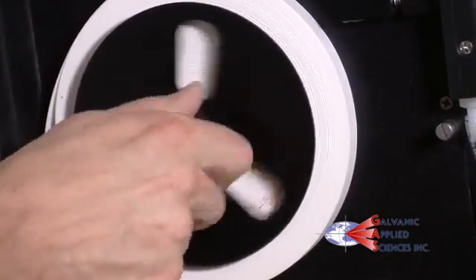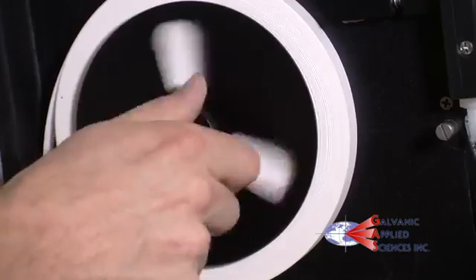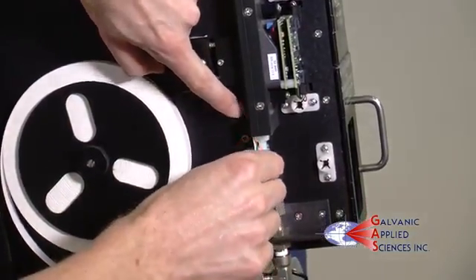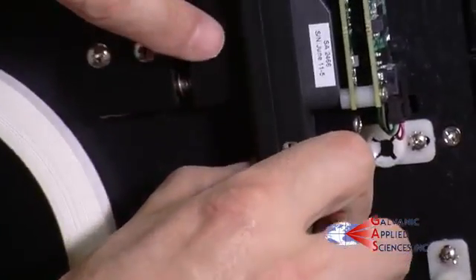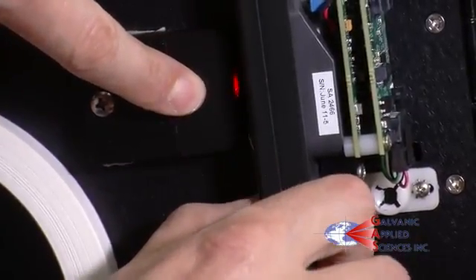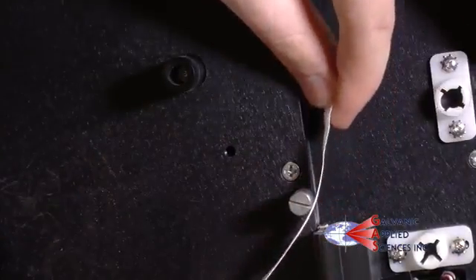Install the new tape on the bottom and replace the guide reel. To feed the tape through the analyzer, start at the lower guide pin, pull back the compression head and slide the tape past the sample chamber. Feed the tape over the upper guide pin and over the tape counter.